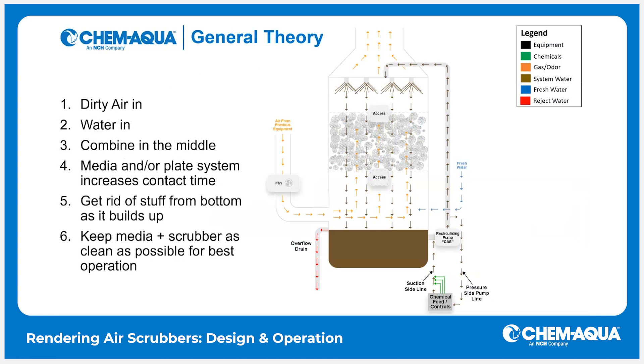A general theory on how they operate: we bring the dirty air in from the cooker or from whatever process, we bring fresh water in, and they combine in the middle. Water is able to capture odors and cool the fats and solids so that they drop out into the bottom sump. We spray it inside the machine right on top of the gas. There's generally media of some sort in the middle to increase surface area and increase contact time of the water and the gas.